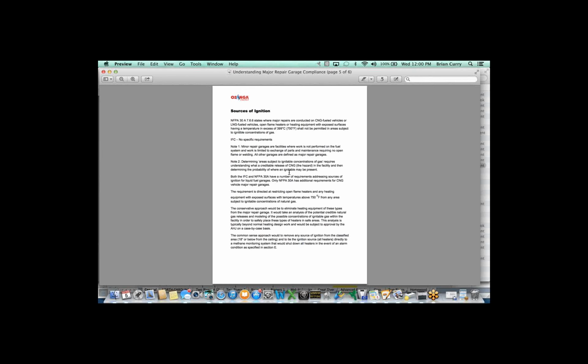So I've always found it's very important to locate the methane detector in the right spot, because that's the area that's going to sense 25% LFL, much higher than where any heater would be located. Assuming I sense the gas at 25% LFL way higher up than where the heater's located, I'm going to trigger that exhaust ventilation that's going to ventilate that shop before the gas has any chance of getting to the point where it's going to be combustible or near a heater.